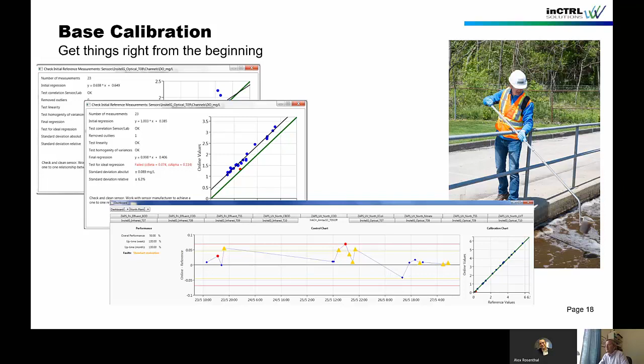For us, that means after initialization we move into normal operation. This is another screenshot of our monitoring control platform where we track the performance in a control chart, and on the right-hand side you can see that the analyzer was properly calibrated. So you can get these instruments to work if you know what you're doing.